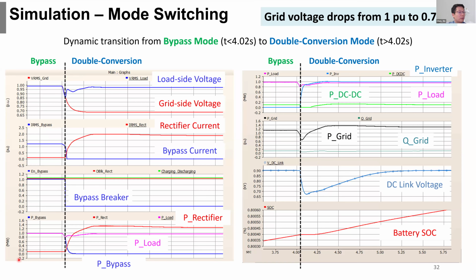Also for the power, this blue curve is the power through the bypass breaker. The power is decreasing from 1 per unit to 0. Then the power from the rectifier is increased to more than 1 per unit because in this case we are also charging the battery. So the total power is the load power plus the battery charging power. But the load power is still maintained at close to 1 per unit, so we have a reliable power supply to the load.